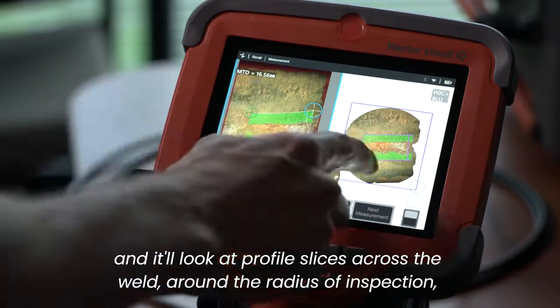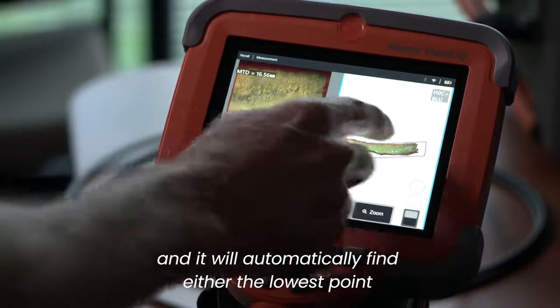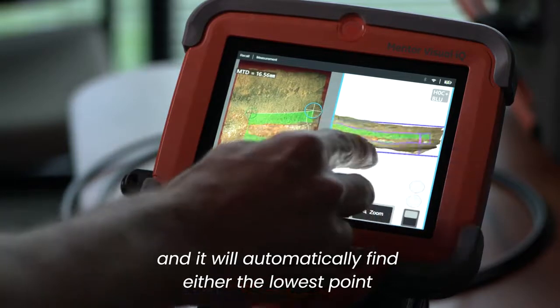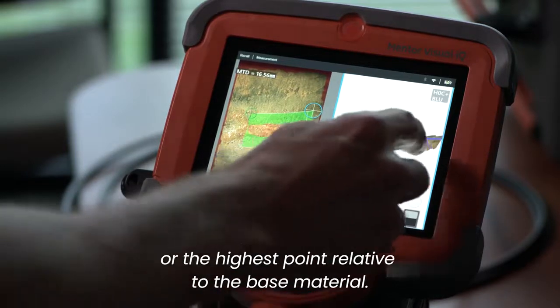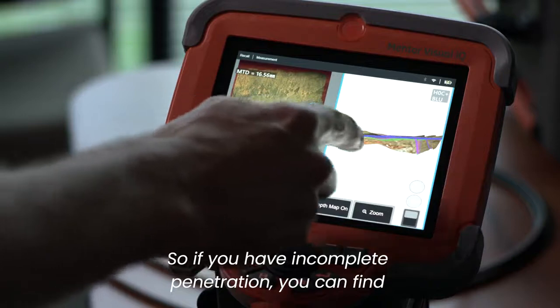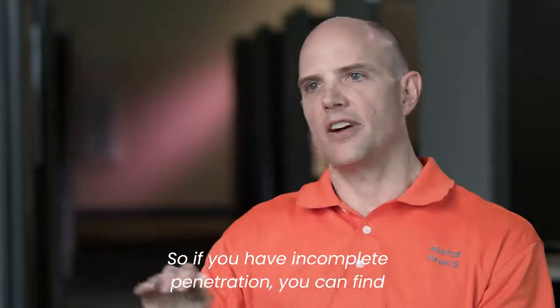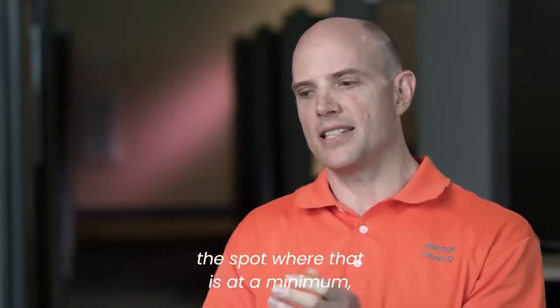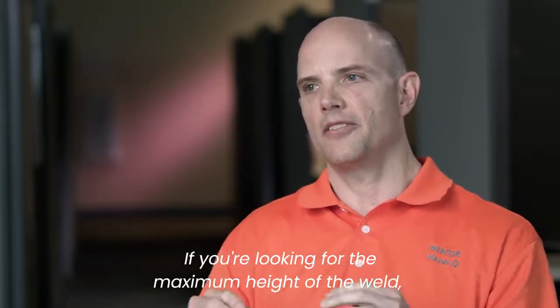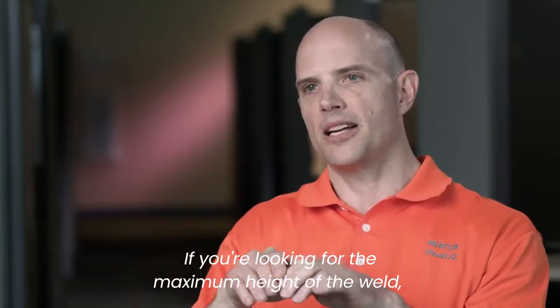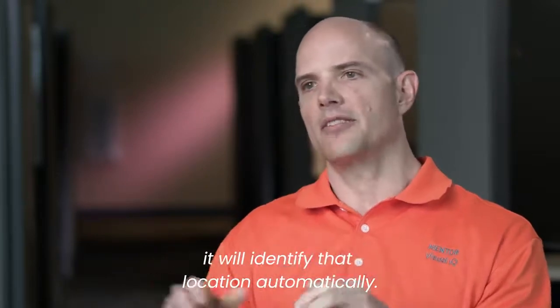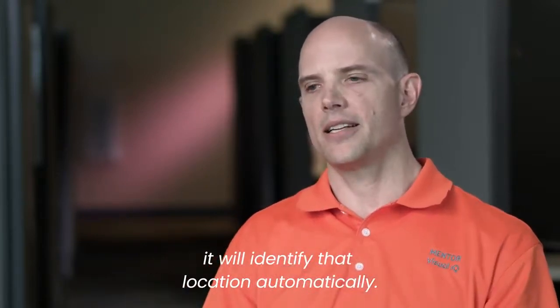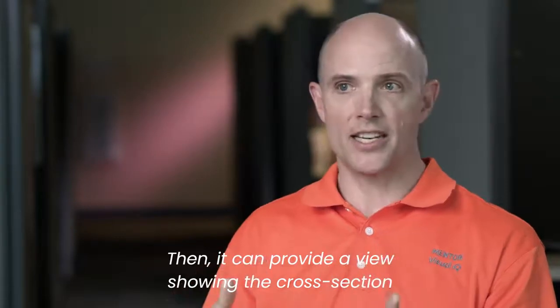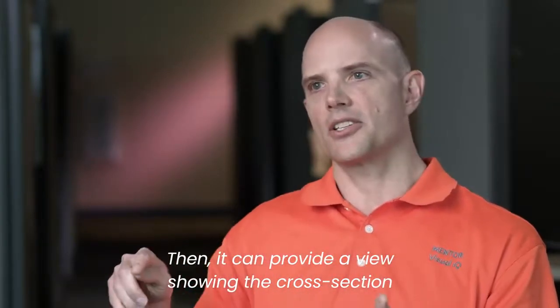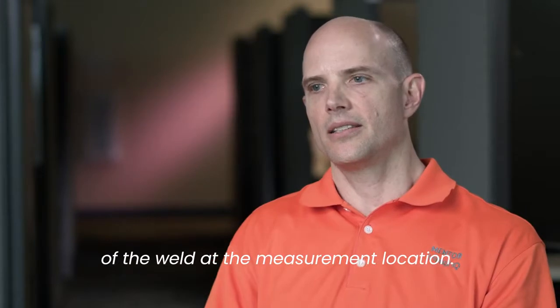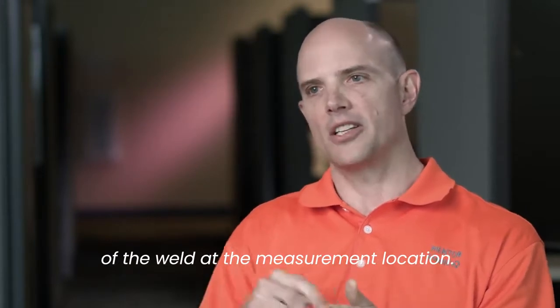around the radius of inspection, and it will automatically find either the lowest point or the highest point relative to the base material. So if you have incomplete penetration, it can find the spot where that is at a minimum, and if you're looking for the maximum height of the weld, it will also identify that location automatically. And then it can provide an additional view showing the cross-section of the weld at the measurement location.